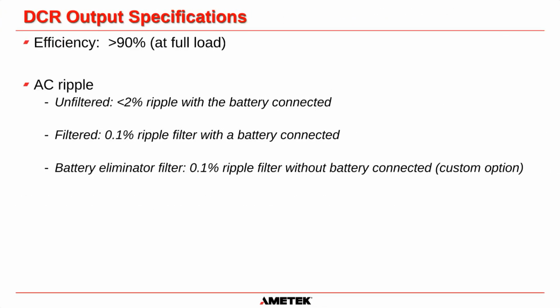Our system efficiencies are greater than 90% at full load. That varies on the size of the charger, but everything is above 90%. And our ripple characteristics are, if we don't have a filter, less than 2% ripple with the battery connected. And we have an optional charger output filter with 0.1% ripple when the battery is connected. And then we have another custom option, which is a 0.1% ripple filter without the battery connected.